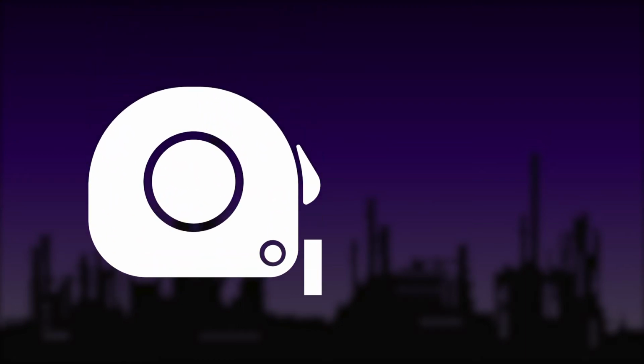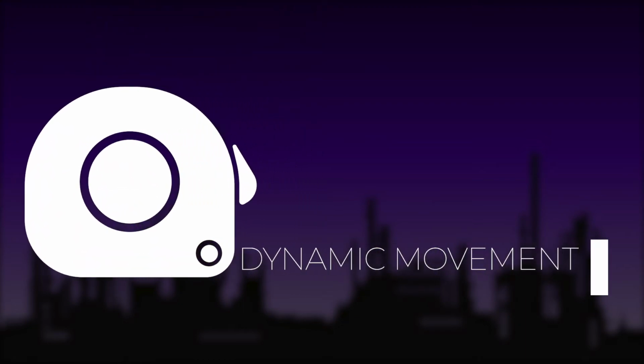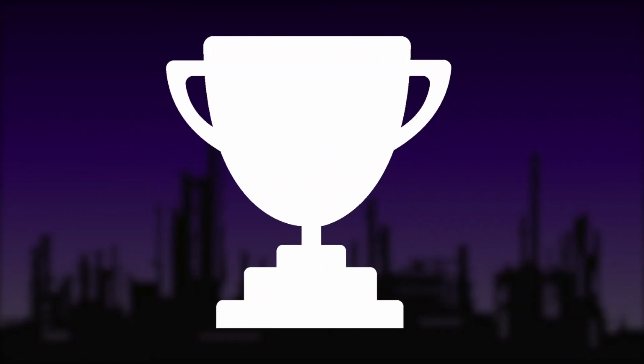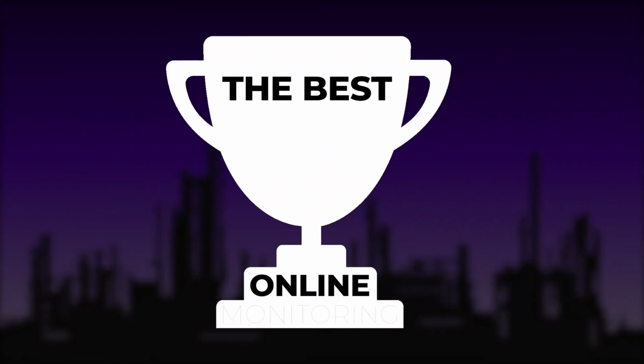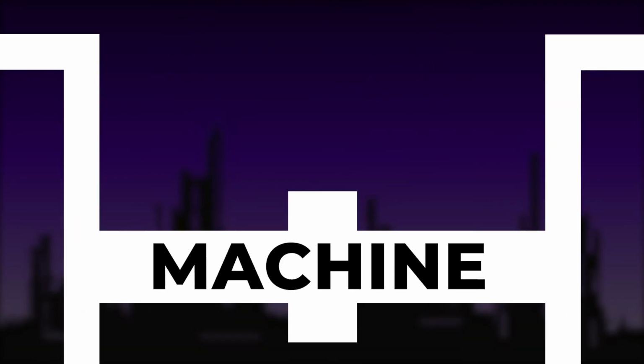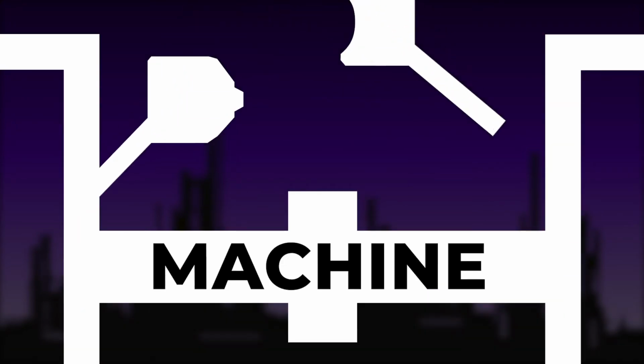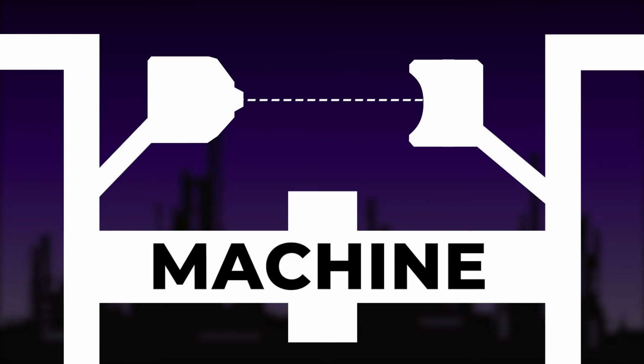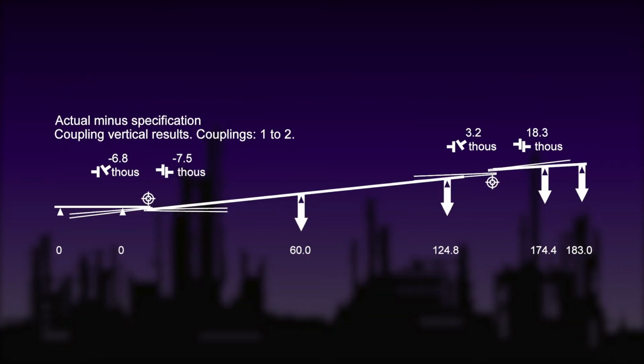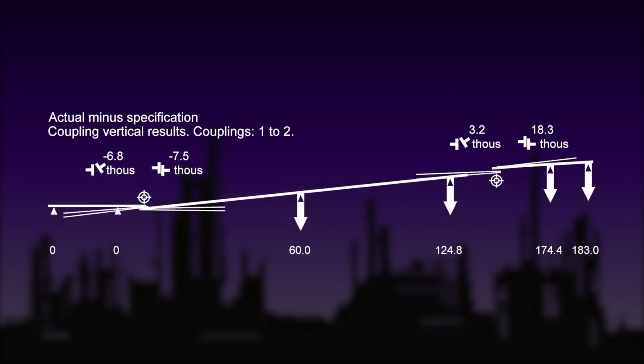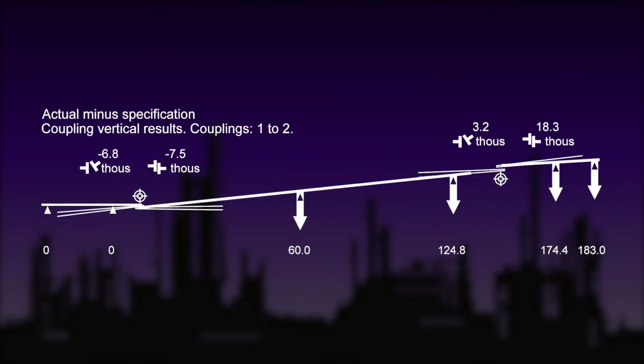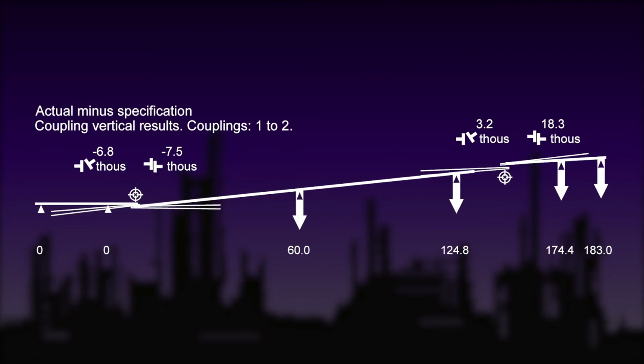The best way to determine the actual dynamic movement of your machine is to measure it. There are a few ways we're able to do this, but the best way is to perform online monitoring. The best way we do this is by hooking up a laser and a target to monitor the movement of the machine. By doing this, we're able to get the horizontal offset, horizontal angle, vertical offset, and vertical angle that happens across the coupling of the machine. We can do this at each one of the couplings of your machine.